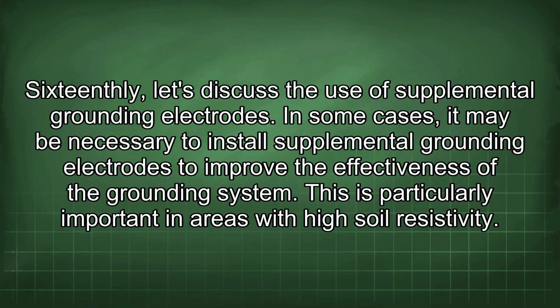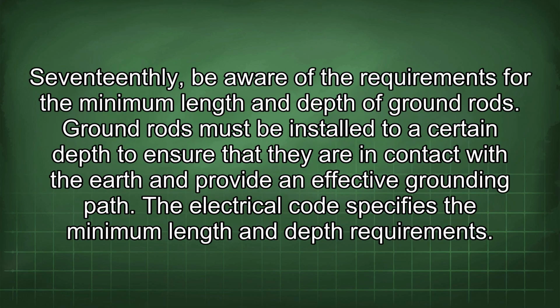Sixteenthly, let's discuss the use of supplemental grounding electrodes. In some cases, it may be necessary to install supplemental grounding electrodes to improve the effectiveness of the grounding system. This is particularly important in areas with high soil resistivity. Seventeenthly, be aware of the requirements for the minimum length and depth of ground rods. Ground rods must be installed to a certain depth to ensure that they are in contact with the earth and provide an effective grounding path. The electrical code specifies the minimum length and depth requirements.